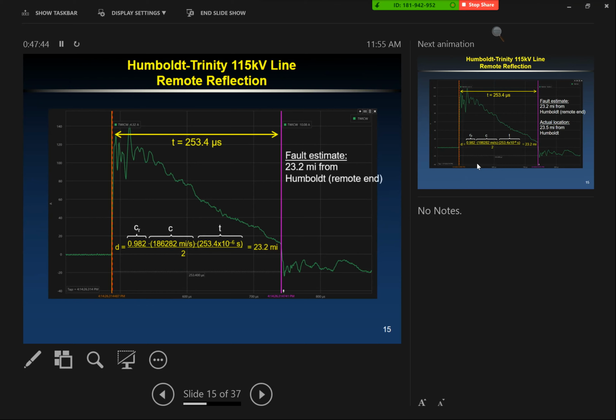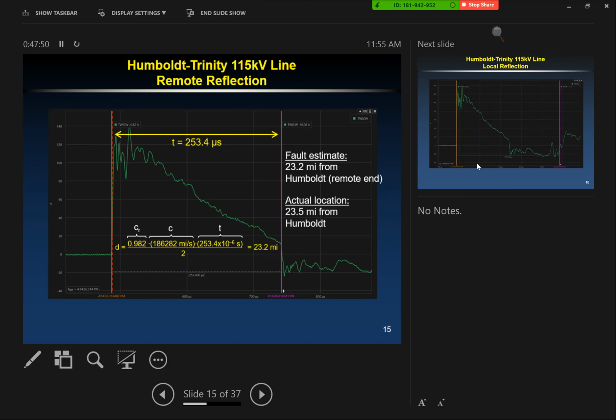So our fault location estimate is 23.2 miles from Humboldt, the remote end. Field reports came back with an actual location of 23.5 miles from Humboldt. For most fault locations, especially single line to ground faults, that's awesome, 0.3 miles off. For traveling wave, that's actually not all that great, they promise within about 0.1 miles, usually one span length. With this very simplistic calculation, I haven't considered things like CT lead length or other errors we'll discuss later. But you can see, even with just a simple calculation, you get within 0.3 miles on a 70-mile long line.